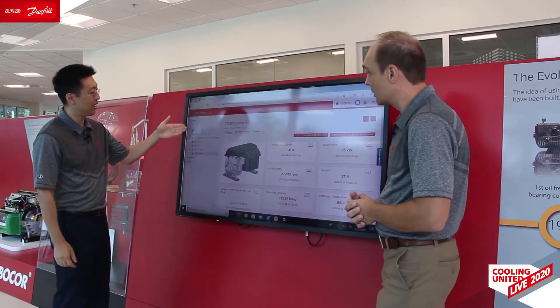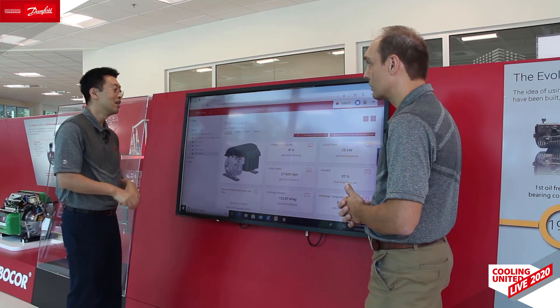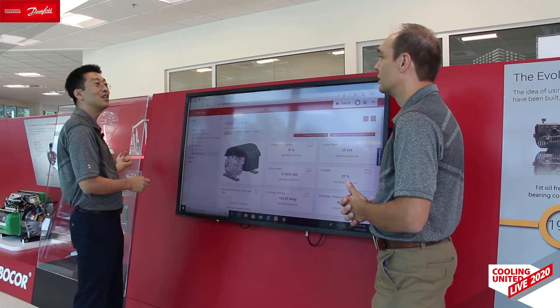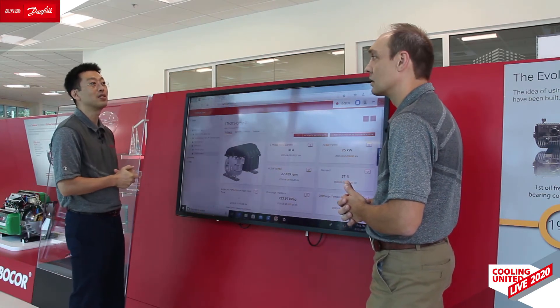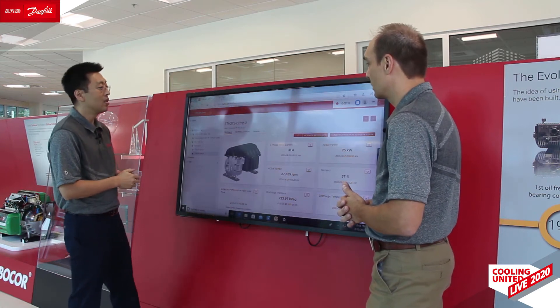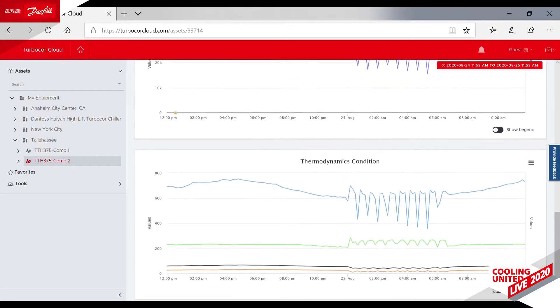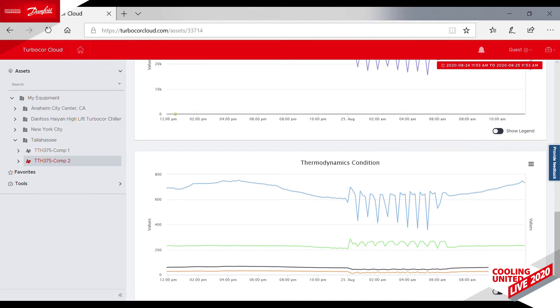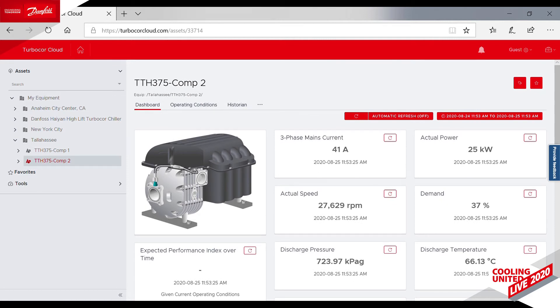Starting from the left-hand side, you have a tree structure — similar to what you're used to with any Windows platform — where you can connect any and all of your accounts and sites globally. Because we're here in this building today, I have connected the chiller and the compressors servicing us right now. These are the two Turbocor High Lift compressors out there, and all the data in real time are displayed here on the dashboard. You can see your thermodynamic conditions, your power conditions — and this is live from what's happening right now.